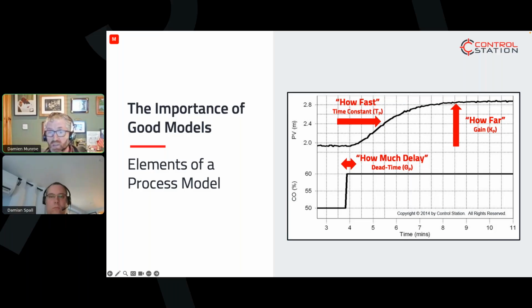You can get a ratio there - it's called the process gain. The process time constant is how fast, how quickly does the process move? It's a time period. Notice that arrow was not pointing at the top of the curve - the process time constant is not the overall time of change. Statistically it's 63% of that time, somewhere a little over halfway, is where it's calculated.